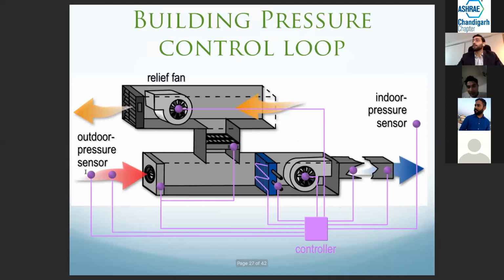And now we'll talk about building pressure. In this scenario, we have an outdoor pressure sensor, an indoor pressure sensor, and a relief fan. Sometimes what happens is you're trying to enter a building and you try to open the door, but the door's so jammed in that you're doing a workout opening the door. Or sometimes it's the opposite: you go to a building and the door's already trying to blow open all by itself. So what's happening in that building is the pressure is off.